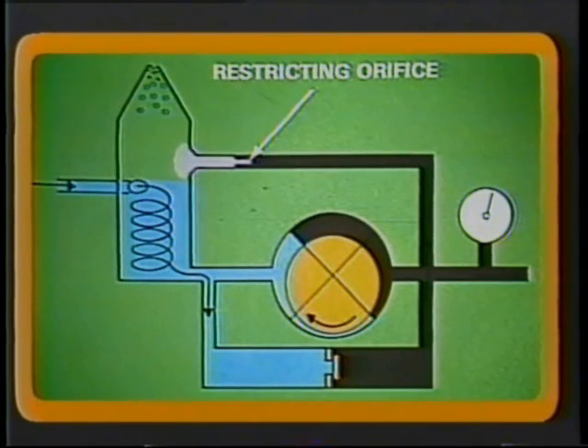By installing a restricting orifice in a return line between the pump outlet and inlet, we can control the amount of fuel delivered to the engine, and the pressure of this fuel can be made to vary with the speed of the pump.